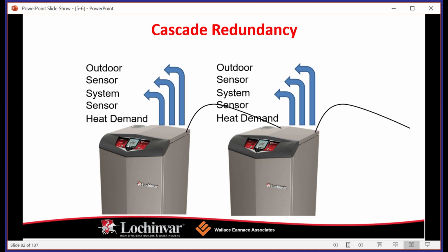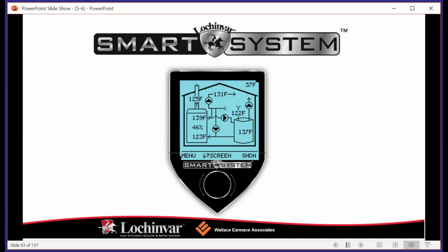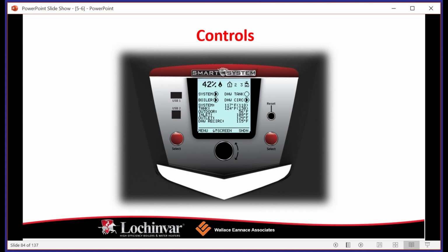Again, efficiency and redundancy. Okay, so here's a capture of the smart system. Yeah, the smart system is in English, okay? All of the controllers that you get on Lochinvar are meant to run where the UI is almost like an iPhone or an iPad, right? When you get this thing out of the box and you set it up, you're not getting a million different things where you need to be an engineer and dial down through 100 different submenus to set it up. It's going to have a wizard that's going to walk you through, and it's going to ask you what you want to do, and you're going to set it up, and it's very simple.